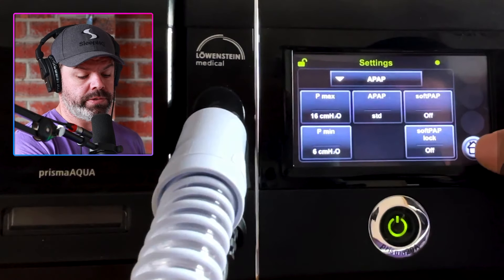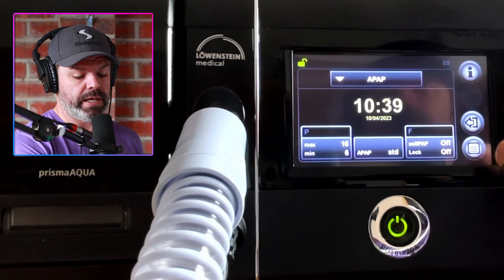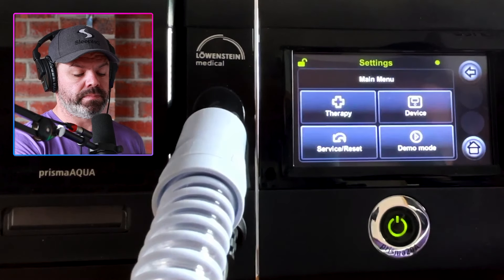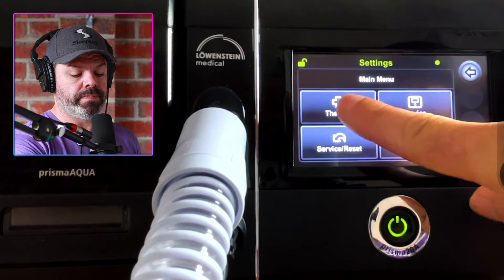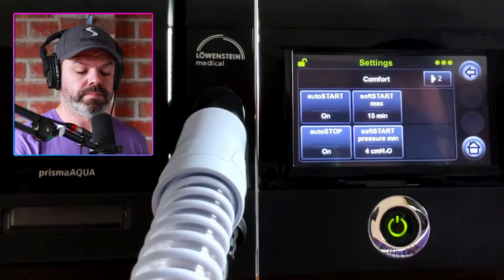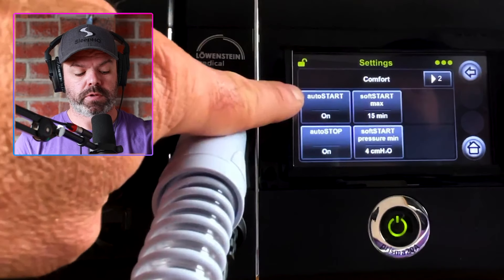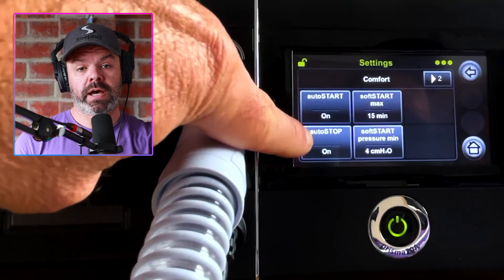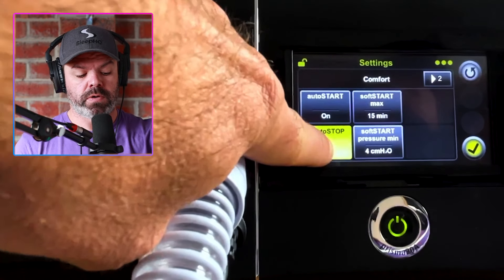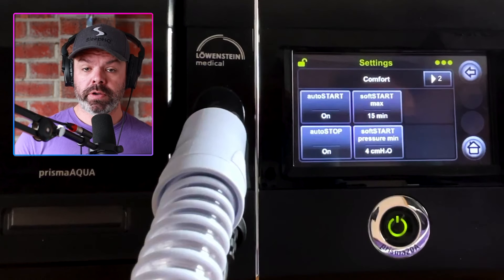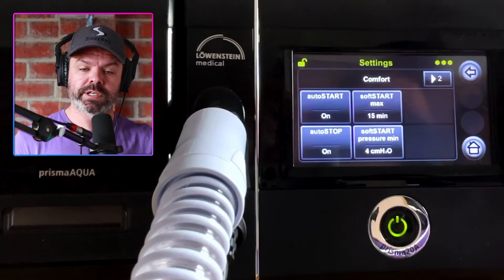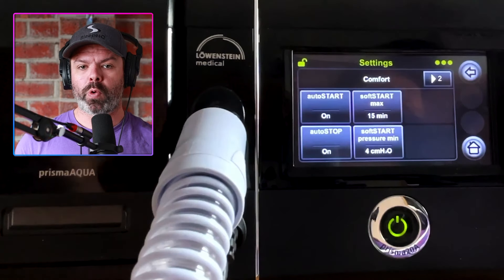Now we'll go to home, then click this icon down here, click therapy and then comfort. Auto start on or off — we can change that. With auto start on, you put your mask on, start breathing, and the machine starts automatically; take your mask off and it will automatically stop.